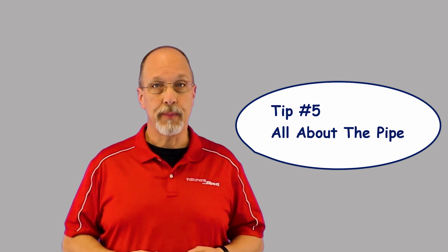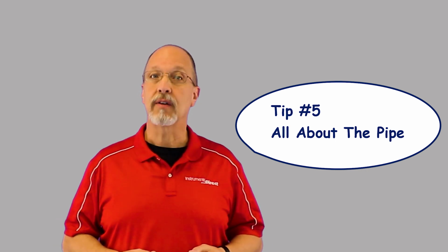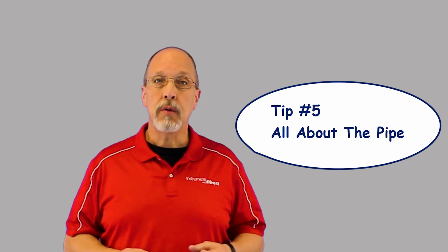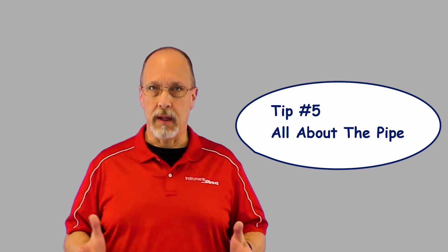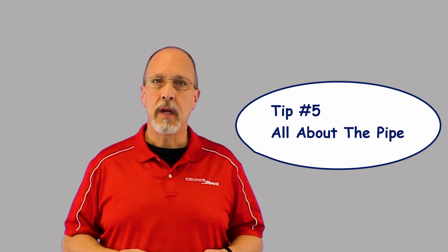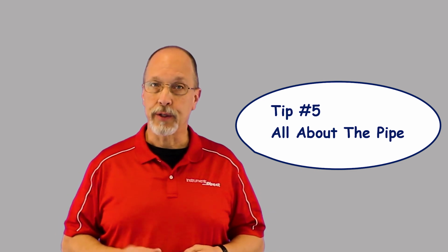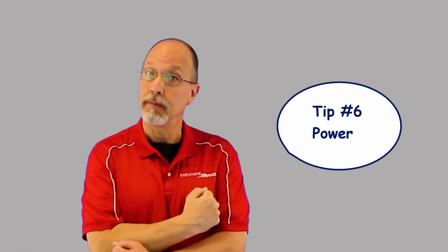The pipe chart usually comes with most flow meters, or I'm sure you can find one on Google. In most cases, metal and PVC pipe will be Schedule 40, ductile iron, Class 52, and copper tubing is usually Type L. Everything else, well, you better check it out on a pipe chart. Make sure you're right.